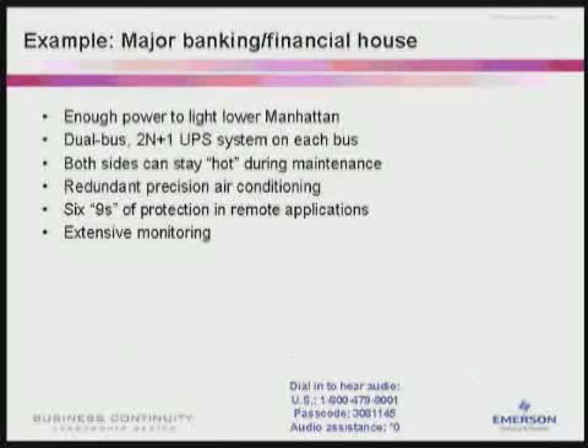Finally, we have a major banking and financial firm. Their facility uses enough power to light Lower Manhattan. The power is protected by 2N UPS systems with maintenance bypass capability, so the organization is always operating with twice the required amount of power for full system protection. By maintaining an extra available UPS and by using static transfer switches, the organization can keep single and dual-corded load equipment fed and with conditioned power at all times. Equipment is cooled by redundant precision cooling systems. All remote applications are protected to 6 nines reliability by incorporating the same online double conversion UPS technology there.